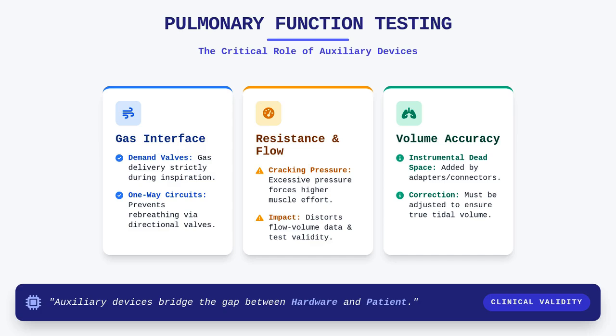We must understand the mechanics of demand valves, which are designed to deliver gas only during the inspiratory phase, and directional breathing circuits that rely on one-way valve systems to prevent rebreathing. The design specifications for these components are not arbitrary. They are governed by strict resistance parameters across high flows to ensure that the patient's respiratory effort is not artificially impeded by the equipment itself.